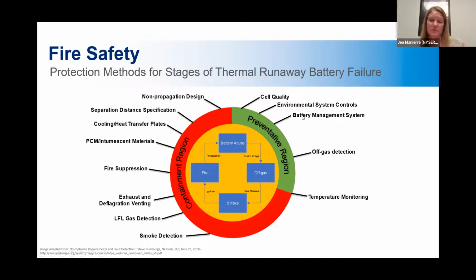So those are all great preventative measures to begin with, but we didn't want to stop there because things can happen, things can go wrong. So in the unlikely event that the battery management system is not able to nip it in the bud, we have off-gas detection requirements. So if those cells are heating up and starting to off-gas, you have gas detectors in there that can notice that and set off alarms as well. Beyond that, say for whatever reason the off-gas detection fails, there's the temperature monitoring. So if it's starting to heat up in there, even if you're not noticing the gas, you're going to notice the temperature of them. Beyond that, working our way over to like the 6 o'clock mark, if you will, smoke detection, if you're starting to get to that point.